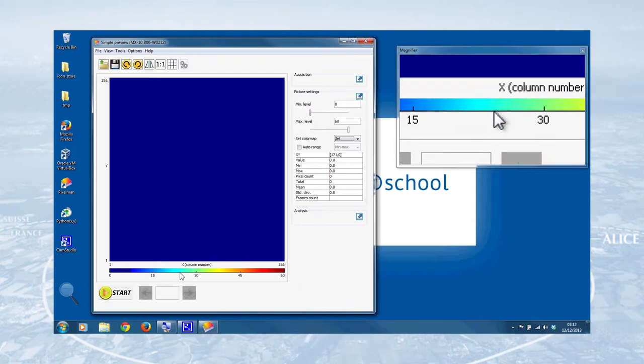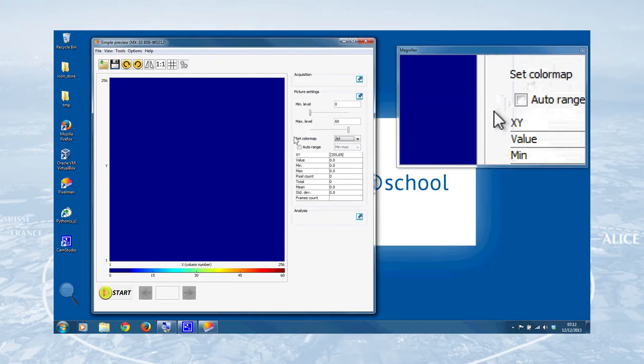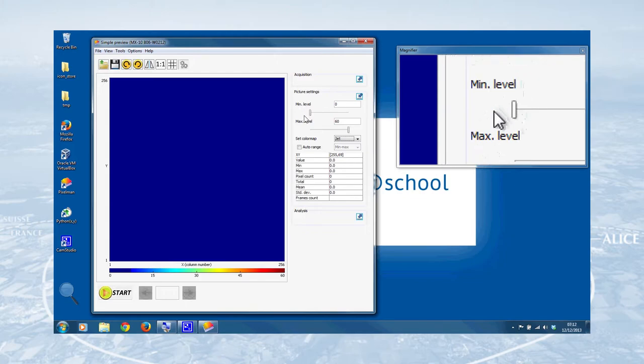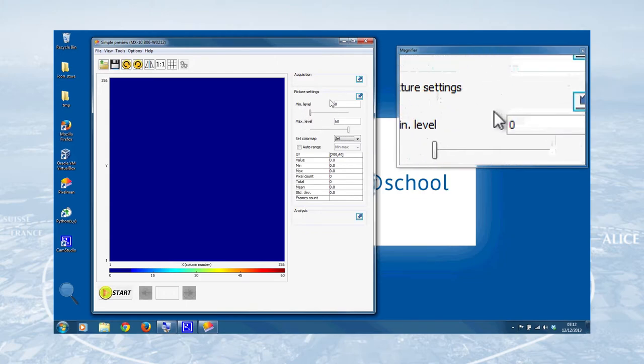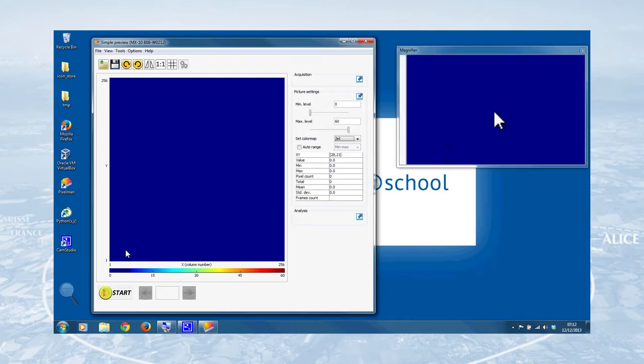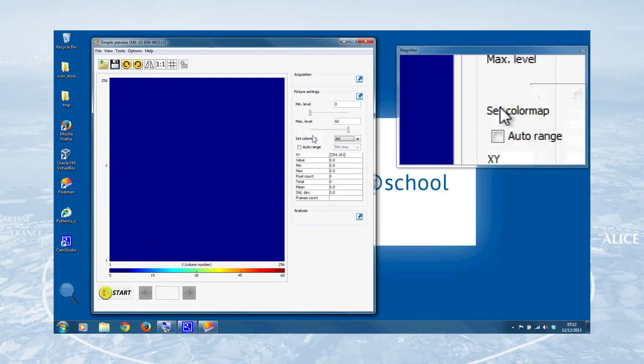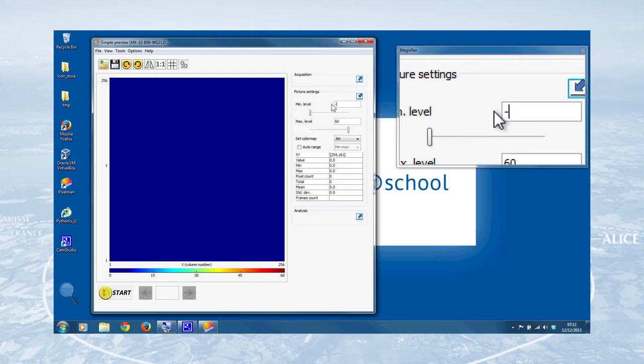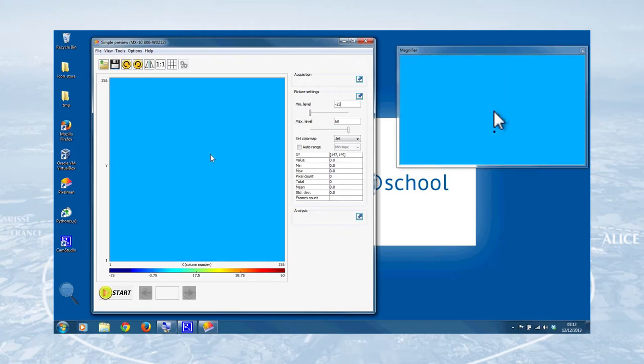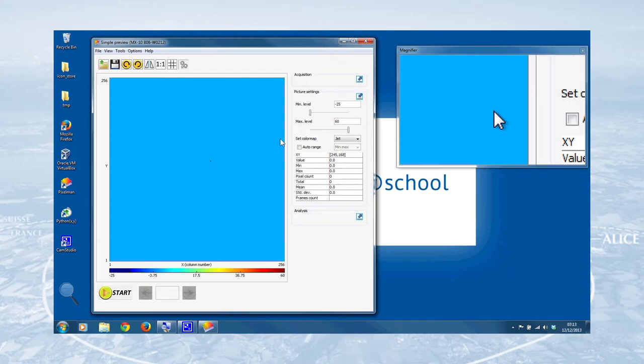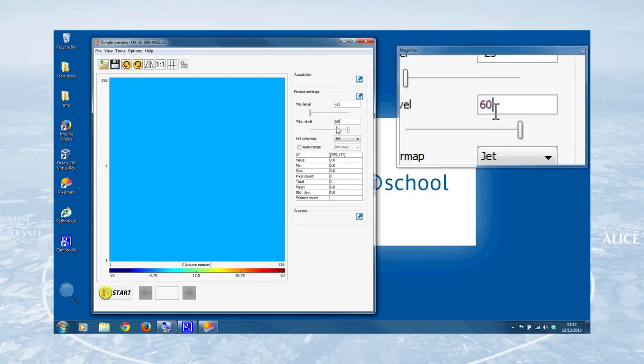And in fact if you want a lighter blue, there's something you can do with the min level and max level of the picture settings here. So this determines what colors are mapped to the minimum and maximum. So the zero is currently this very sort of dark blue here. So actually here's a little trick. If you set this to say minus 25, the base level will become this much lighter blue, making it easier to see the different particles. So we'll leave it like that for the moment. A maximum level of 60 should be enough for the type of particles we'll observe now.